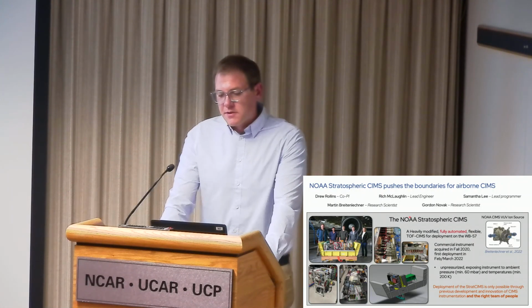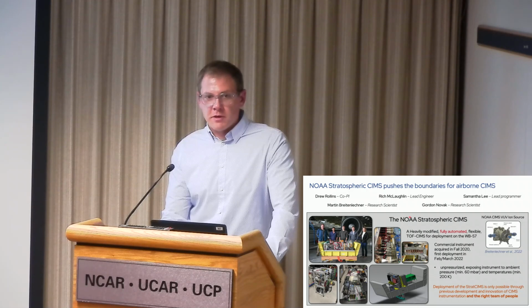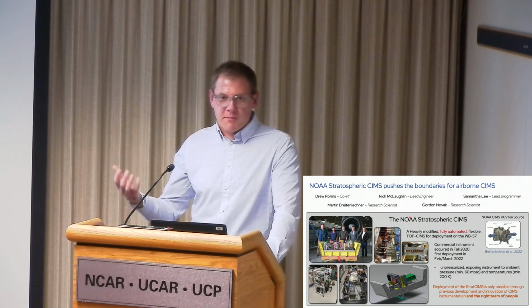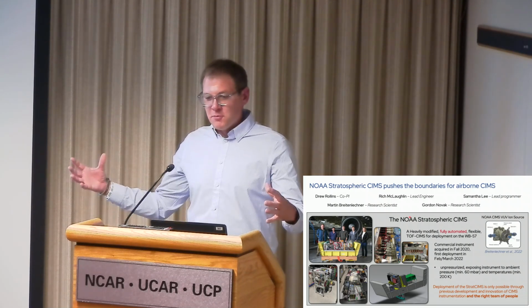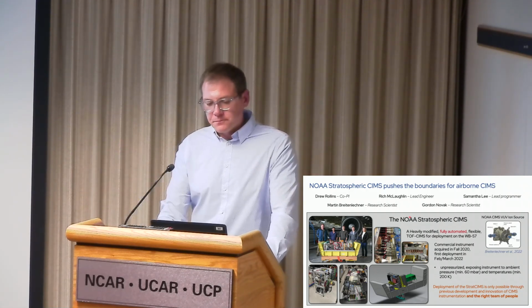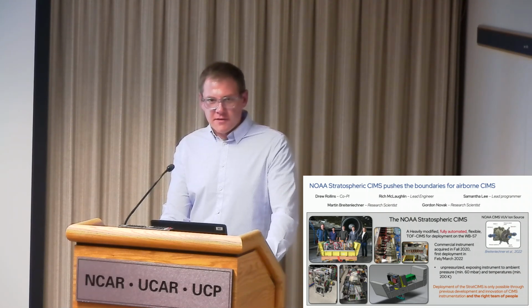Just one other question. Did you say that with your CIMS system you played around with pressurizing it and stuff? No, that was the recommendation from the company. The only iterations of this instrument that have flown in the stratosphere were basically put in a big pressure can. We looked at a radar today, and it was a pressure can in a pod. That's how they said we should fly it, basically build a scuba tank around it and have your inlet coming out of that that's sealed. This pallet bay isn't really built for a configuration like that, the way the instrument came.